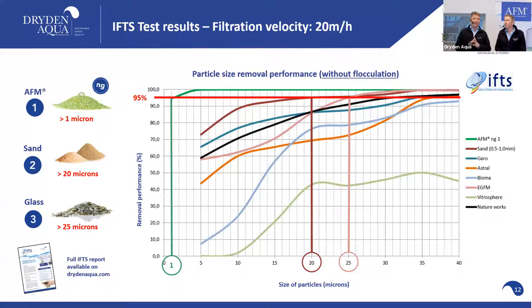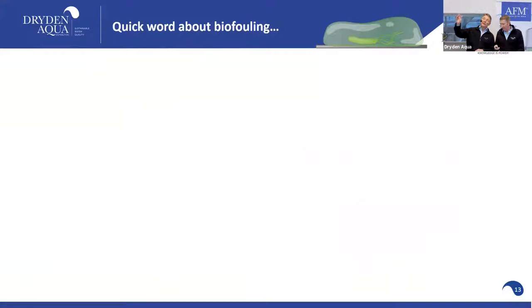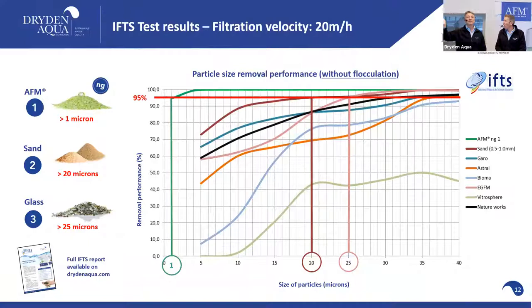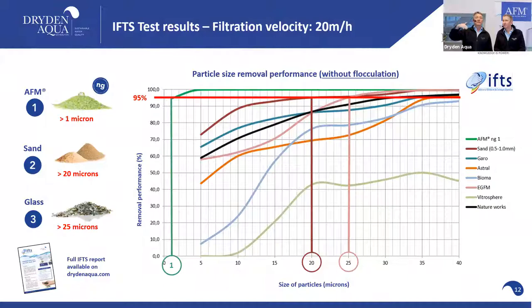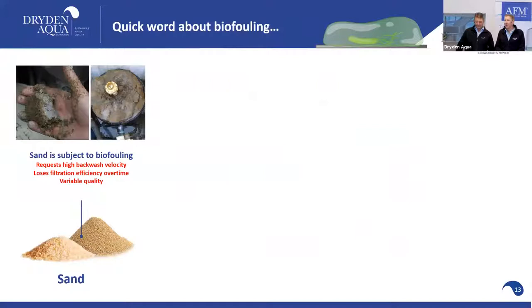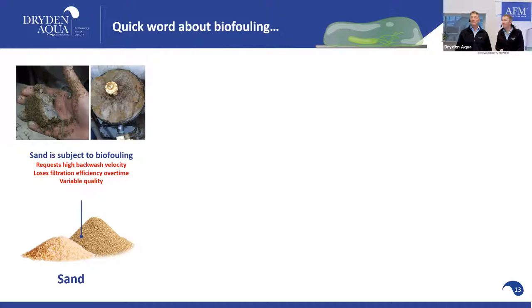Another critical aspect is biofouling. These measurements from IFTS (Institut de la Filtration et des Techniques Séparatives) were done with fresh media at 20 meters per hour filtration velocity with a one-meter filter bed. After six to twelve months, sand begins to biofoul — bacteria attach, form biofilm, the filter channels and loses performance over time.